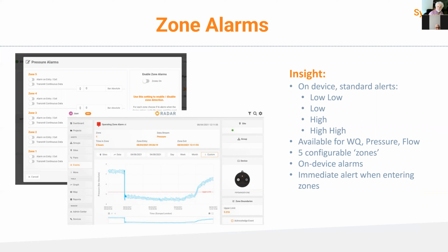So when you start to deviate from your normal expected pressures, you could start to send continuous summary data about every minute so that you can track a potential fault. And when you get to the very high zone, you could send an email alert as well to say that someone really needs to be looking at this now. And when they go there, there's some data leading up to it. So you could configure these for two low and two high alarm levels, or you could set them up to have 4 high alarm levels if you were looking at, say, turbidity, and you were just interested when the signal is high and not when it's down near zero. So those are zone alarms, and they result in email alerts basically coming out of radar.